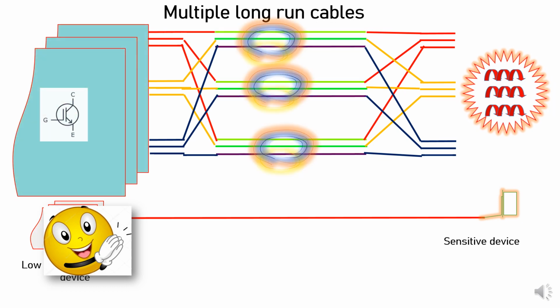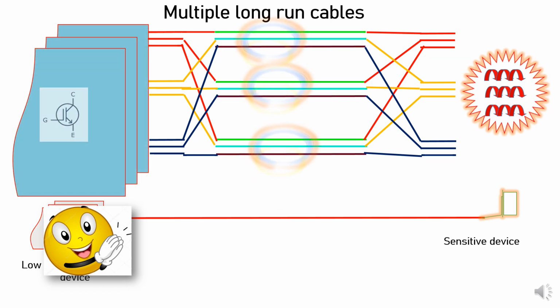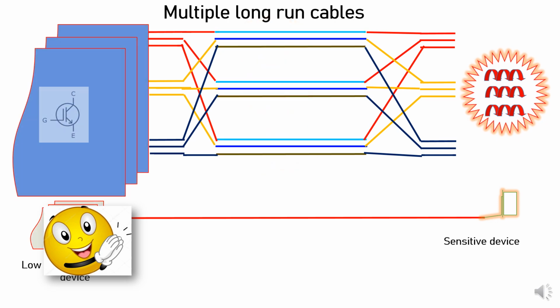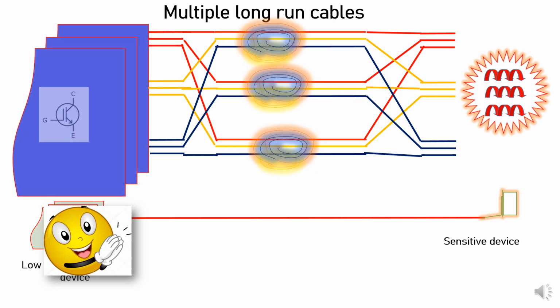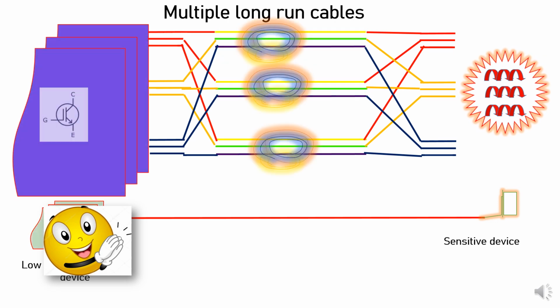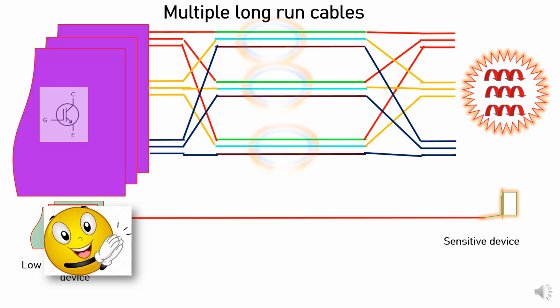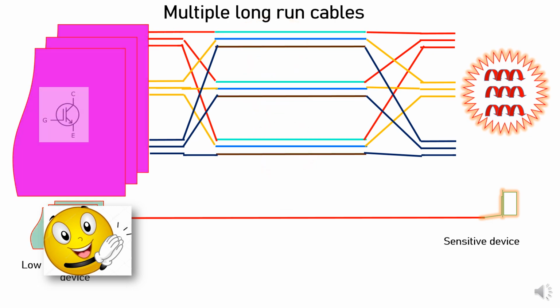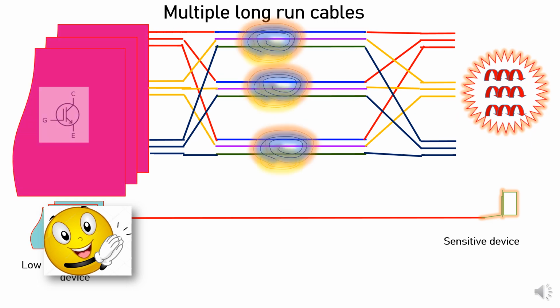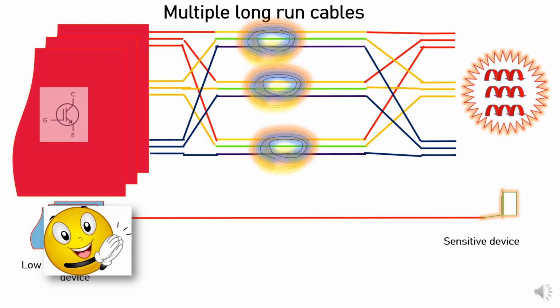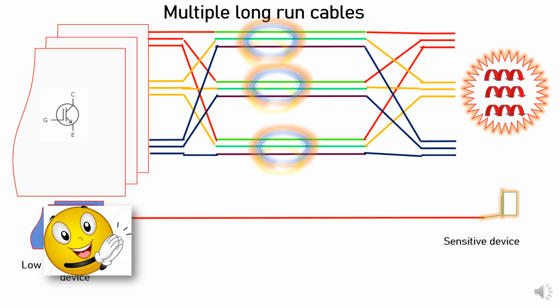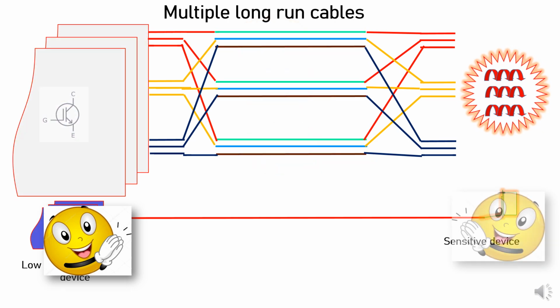The problem for the user is you need to note down the cable connection when you are doing it for the PM and troubleshooting activity, but it's giving a fantastic help in the long run. So no need to worry. You can manage this particular good advantage by doing the transposition connection of the cable at the VSD end as well as the motor end.